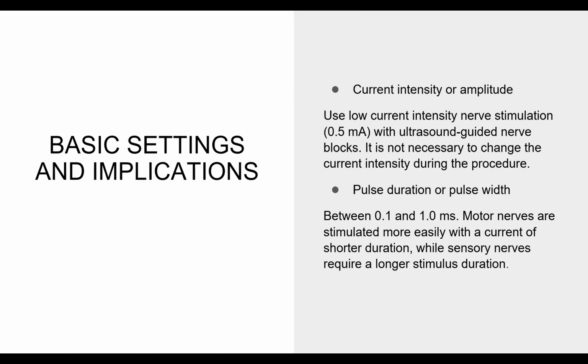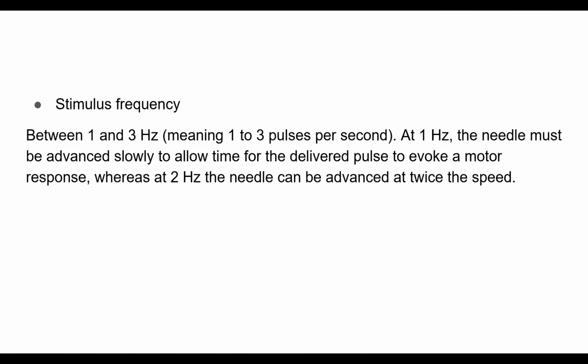And coming to pulse duration or pulse width, between 0.1 and 1 milliseconds, because motor nerves are stimulated more easily with the current of shorter duration because their chronaxy is very less, while the sensory nerves require a longer stimulus duration because of the higher chronaxy.